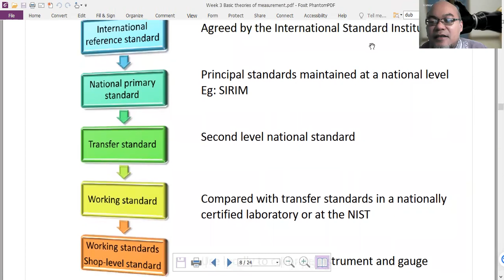you are opening a service in instrument calibration, for example calibrating an ECG, electrocardiography, then you are basically opening a nationally certified laboratory. Your laboratory for standardizing the ECG has to be also certified, and the certification includes a comparison, a calibration with the second national standard, which is then traceable to the national primary standard and international reference standard. Understood? So this is what we call traceability.